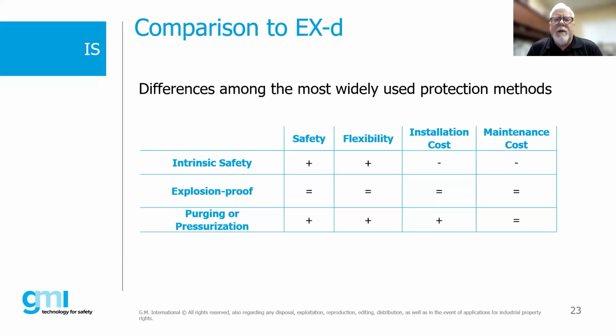And certainly the maintenance cost for intrinsic safety, because generally once it's installed, we don't really have to screw around with it too terribly much. Whereas explosion proof or flame proof, we definitely have to take a little bit more preventative care with regards to things like flanges or threaded designs or the corrosion with cast type enclosures. So just some generalities.